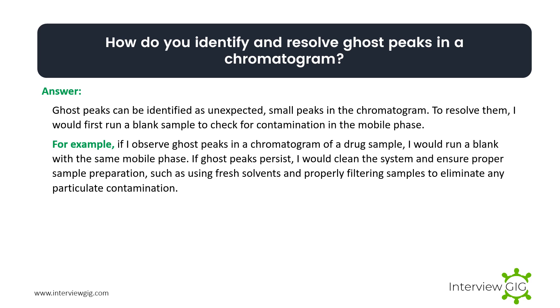How do you identify and resolve ghost peaks in a chromatogram? Ghost peaks can be identified as unexpected small peaks in the chromatogram. To resolve them, I would first run a blank sample to check for contamination in the mobile phase. If ghost peaks persist, I would clean the system and ensure proper sample preparation, such as using fresh solvents and properly filtering samples to eliminate any particulate contamination.